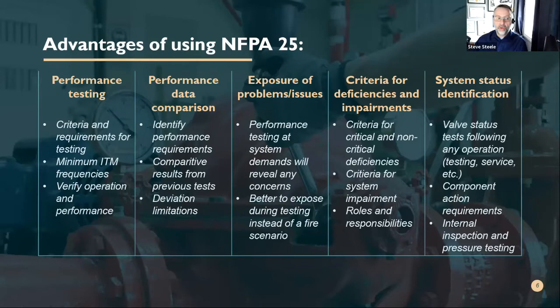Another key point is the criteria for deficiencies and impairments. We can spend a whole day reviewing what is a critical and non-critical deficiency versus an impairment itself. What becomes important is you want to avoid impairments, or more importantly, you want to identify impairments, and that can go so far as not only to the owner, those conducting it, but to the local authority having jurisdiction. When something is impaired, that system has been deemed inoperable and out of service for the most part. That could be as simple as a fire pump out of service. Even though water can be delivered, can it be delivered to the performance requirements of that system itself?